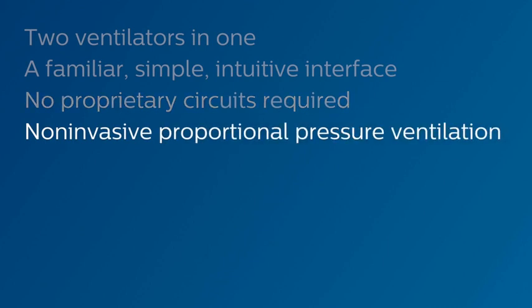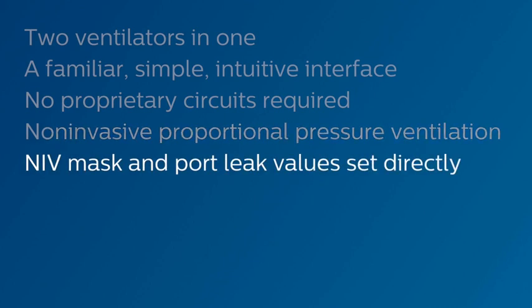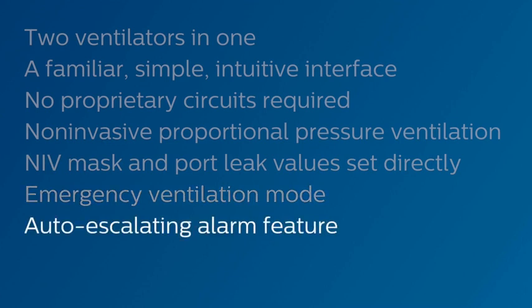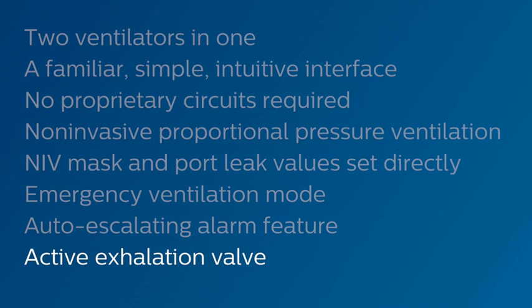Non-invasive proportional pressure ventilation with dynamic elastance and resistance calculations to guide patient setup. NIV mask and port leak values set directly, saving setup and testing time. Peace of mind with the emergency ventilation mode. An auto-escalating alarm feature that increases the output volume of a high-priority alarm if not dealt with within a timely manner. And an active exhalation valve in pressure control ventilation to help improve patient ventilator synchrony.